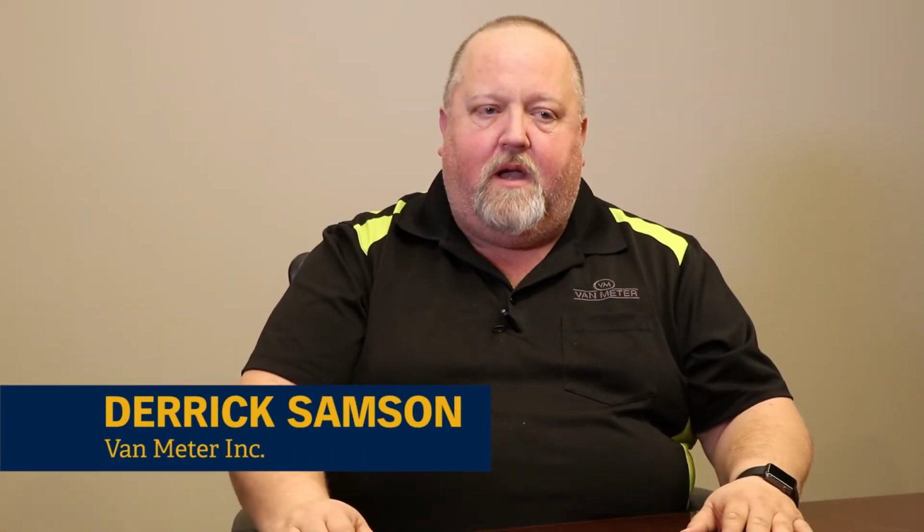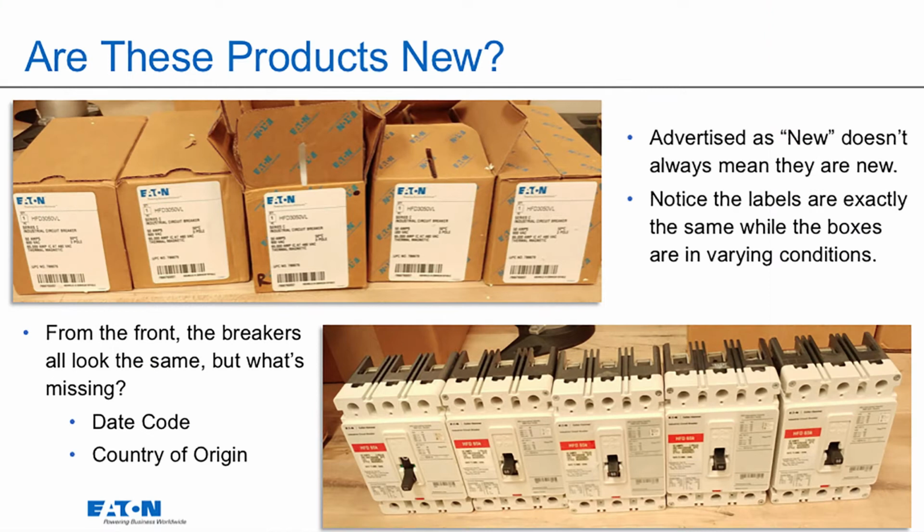With the gray market breakers, they're not guaranteed to be new breakers. I mean, they may have been made in China. They may have been bought from a contractor somewhere else that had excess inventory. They say new, they say refurbished. There is no way to refurbish these molded case breakers. What they do is wipe the dust off them. So you might be getting used equipment. It's just a risk that you shouldn't be willing to take.